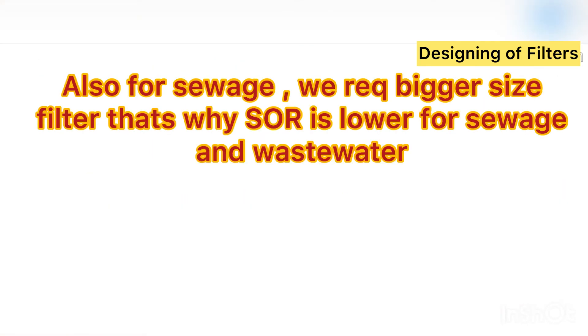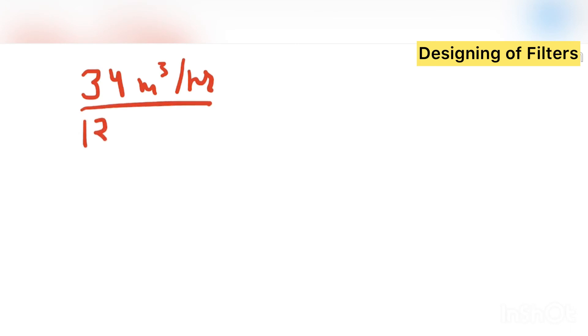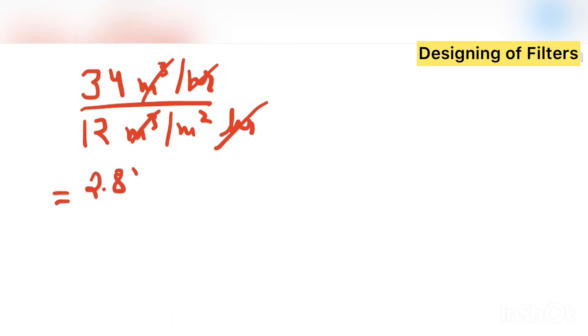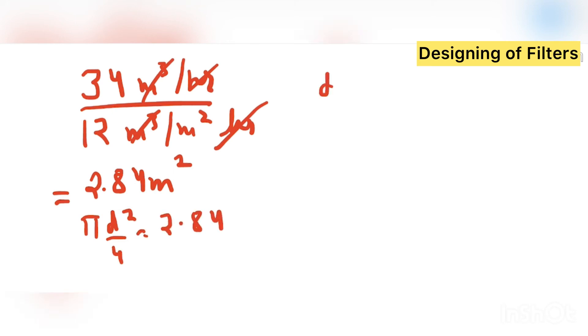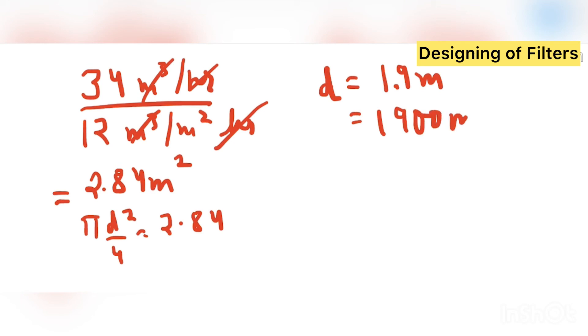Now I will divide 34 meter cube per hour by 12 meter cube per meter square hour. So what I am getting is 2.84 meter square as area. So area, what we call it, pi d square by 4 equals 2.84. So from here the d what I am getting is 1.9 meter, that is equal to 1900 mm.